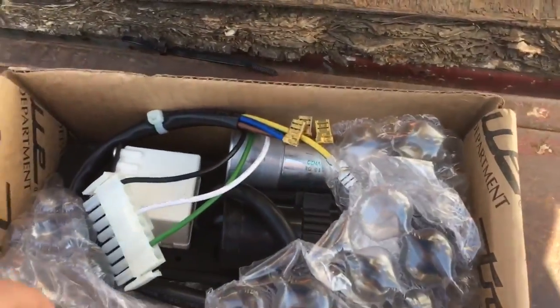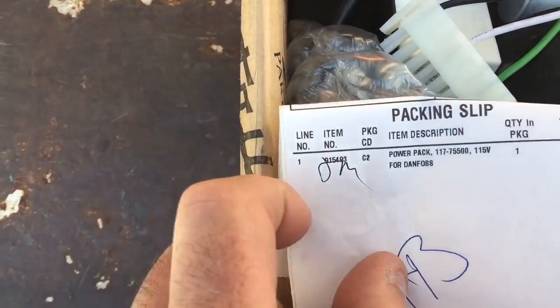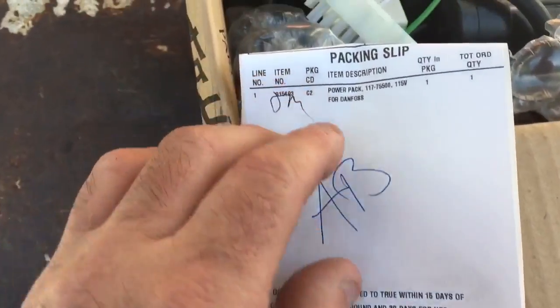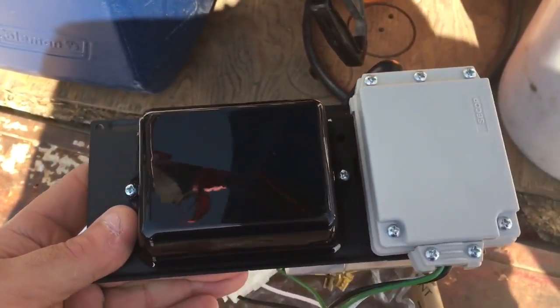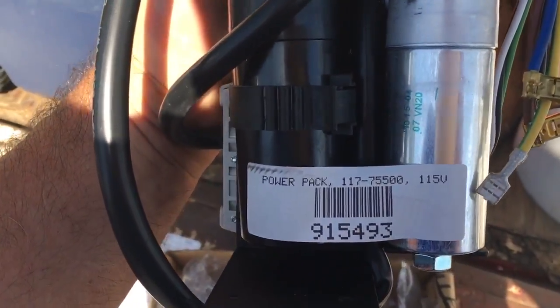Let's see if it goes well. I don't know where the part number is, but here's the packing slip — this is the power pack, 115 volt, for the Danfoss compressor. It's got a module on the back, a connection box, start relay, start and run capacitor — all fancy euro stuff — to the tune of about $268 bucks.